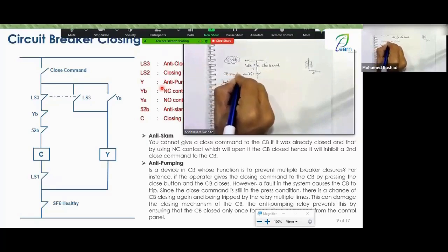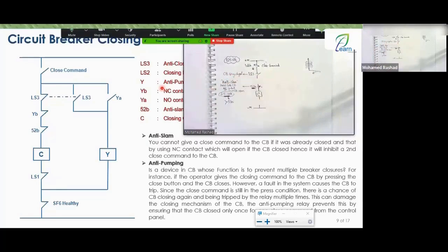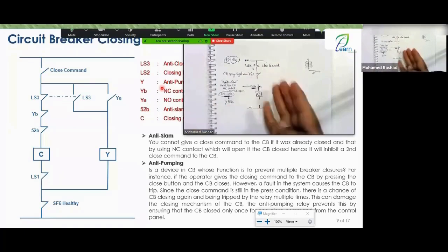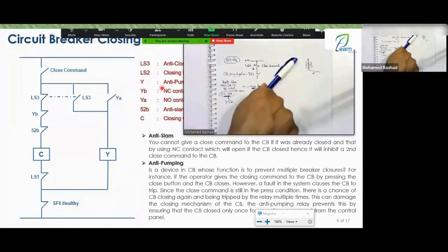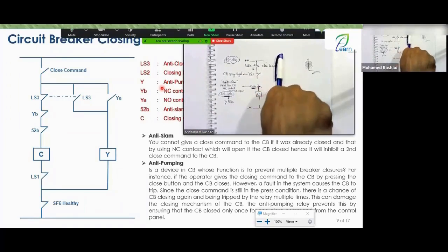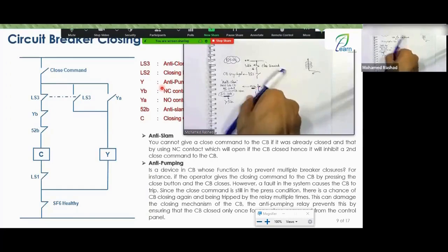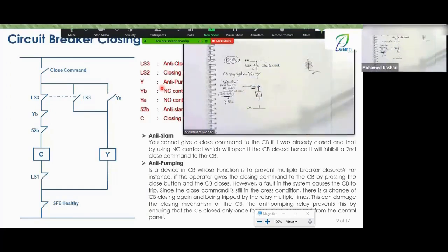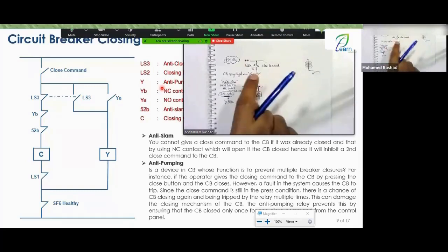It is fully charged, meaning as long as the spring is charged, this contact is closed. If the spring is not charged, this contact is open. So if you give a close command, the DC won't reach the close coil, to prevent it from burning. This is the second reason. The first reason is if you give a close command to a breaker that is already closed and try to give another close command, you might wonder why the breaker isn't responding. The solution is that I created a normally closed contact from the state of the circuit breaker and called it anti-slam. This contact is closed if the breaker is open, and if the breaker closes, it opens to prevent a second close command from reaching the breaker if it is already closed.